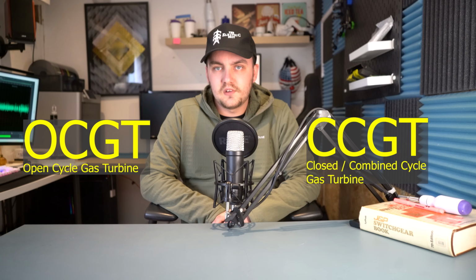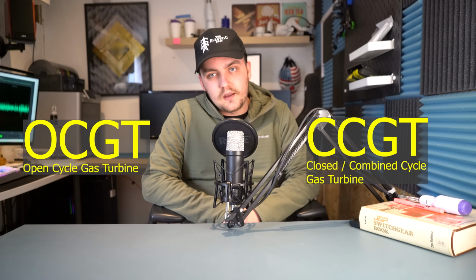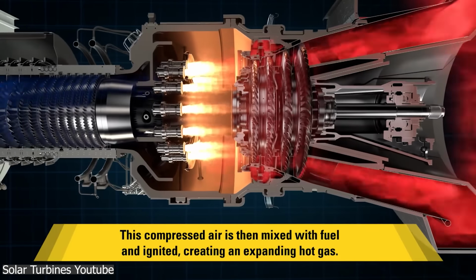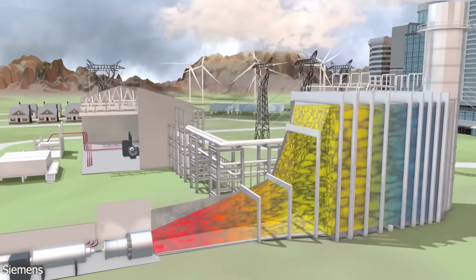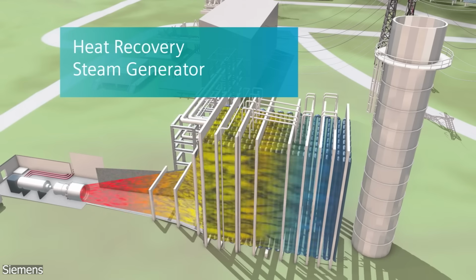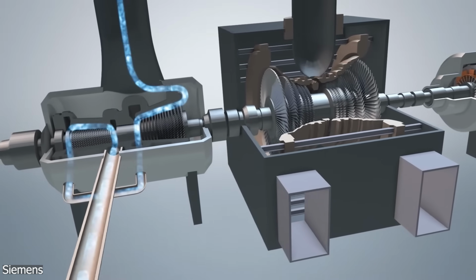So what about gas? Well, there's two types of gas turbine in use, and those are open cycle gas turbine and closed cycle gas turbine. Open cycle operates like a jet engine, where you burn fuel to turn the turbine, so it takes very little energy to start, whereas closed cycle uses an additional steam turbine, which is a lot more sensitive to start up. A lot of modern CCGTs can run in open mode for black start flexibility, using a diesel generator to start. So to round that out, hydro, battery, open cycle gas turbine and some newer solar and wind can all be used to black start.